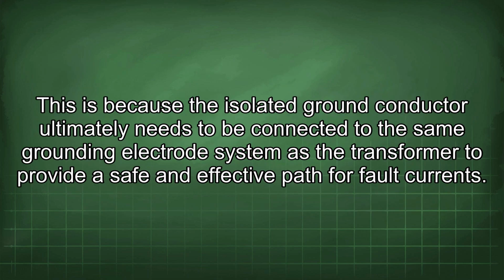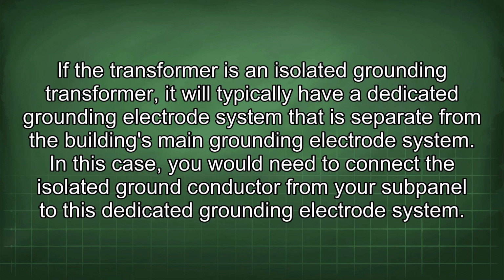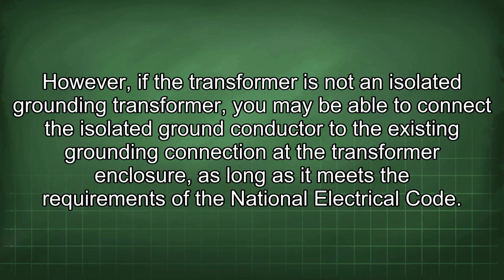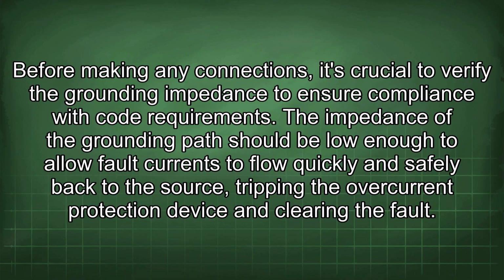This is because the isolated ground conductor ultimately needs to be connected to the same grounding electrode system as the transformer to provide a safe and effective path for fault currents. If the transformer is an isolated grounding transformer, it will typically have a dedicated grounding electrode system that is separate from the building's main grounding electrode system. In this case, you would need to connect the isolated ground conductor from your subpanel to this dedicated grounding electrode system. However, if the transformer is not an isolated grounding transformer, you may be able to connect the isolated ground conductor to the existing grounding connection at the transformer enclosure, as long as it meets the requirements of the National Electrical Code. Before making any connections, it's crucial to verify the grounding impedance to ensure compliance with code requirements.